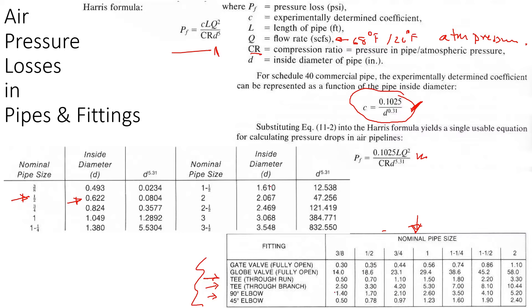What is equivalent length? These fittings lose more than a straight pipe. Equivalent length for this T is 4.2. What that means is a 4.2 feet of straight pipe has exact same loss as this connection. So we can simply add 4.2 feet of length with this L and we are accounting for this T. Just add all the connections and pipes and then input the total length in this equation.